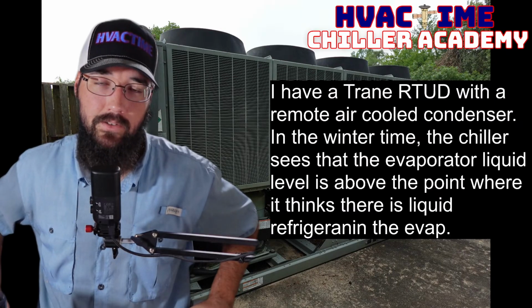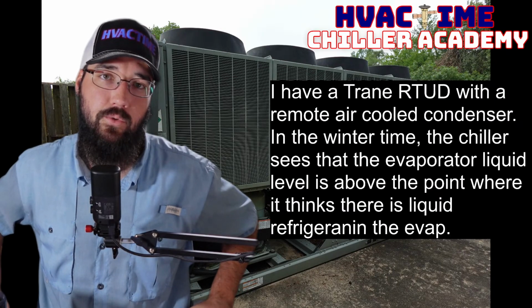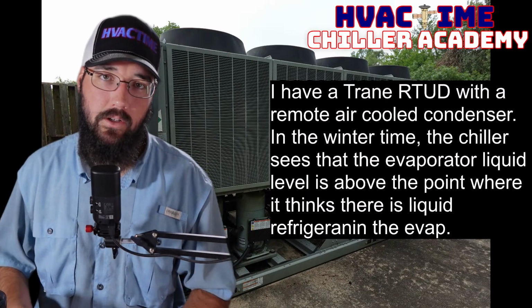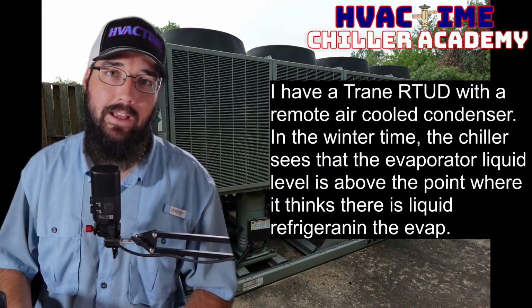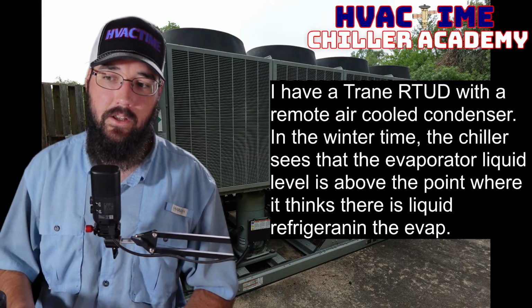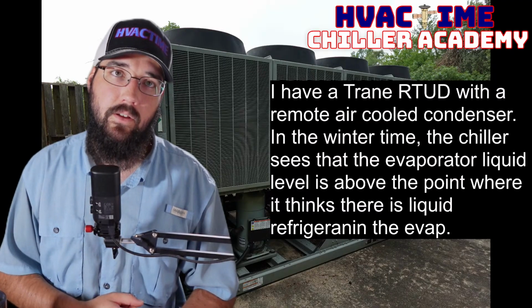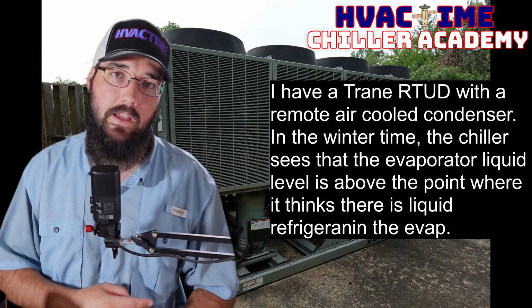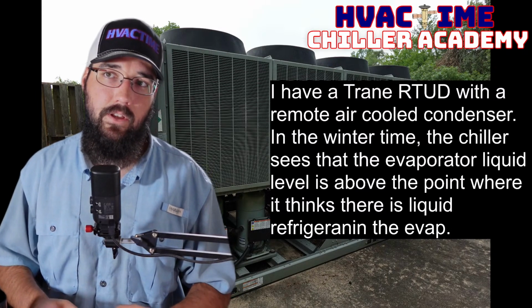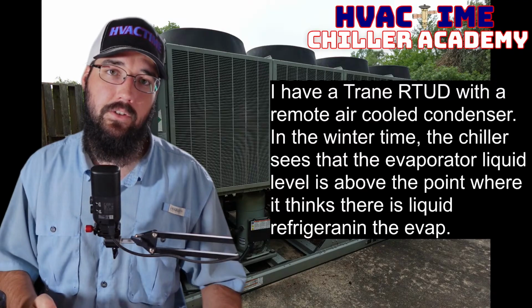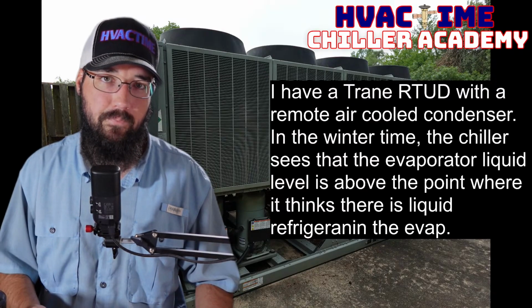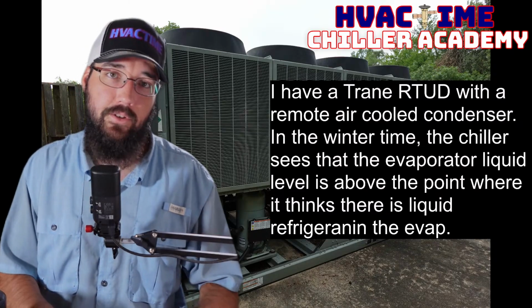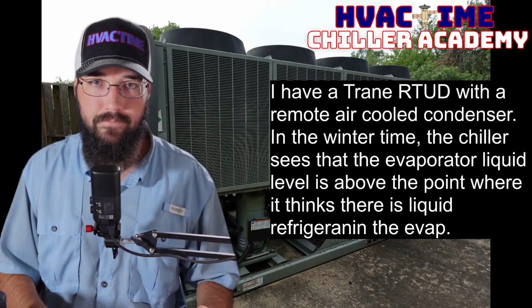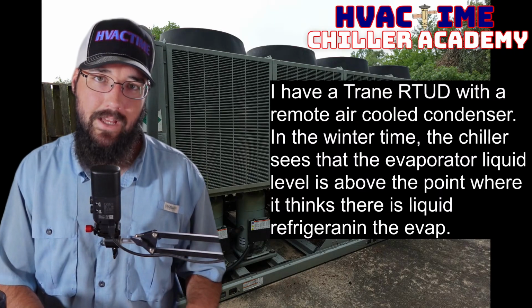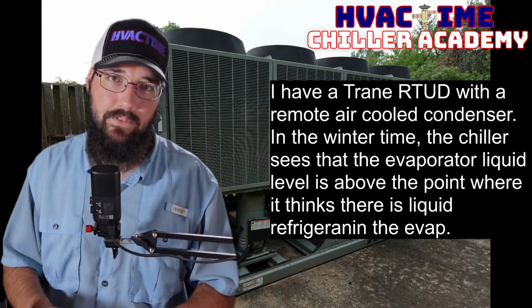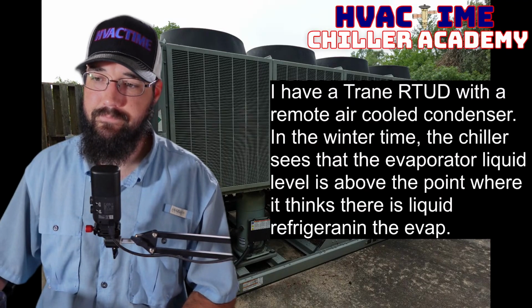Having such a short run cycle, you will start to stack more and more liquid refrigerant into the evaporator. You're not giving the recovery circuit enough time to return that oil back. Because of that, it will just continuously stack and then cause the migration symptoms you're dealing with. Now, everything else we've talked about in terms of head pressure and all the other stuff will play a part. Those things need to be dialed in as well, but we have to give it runtime.